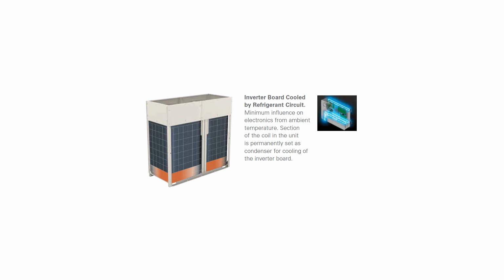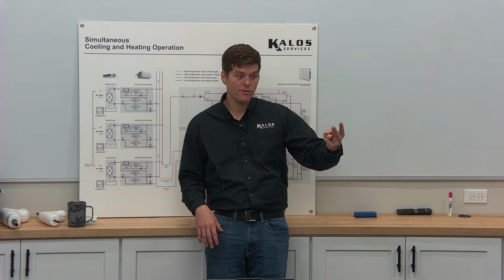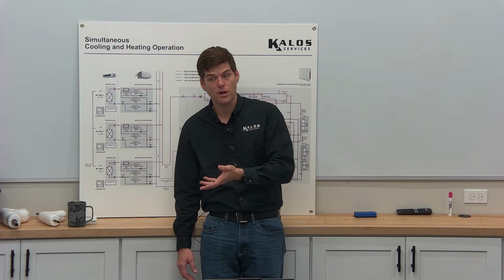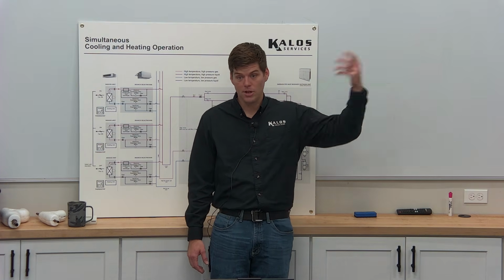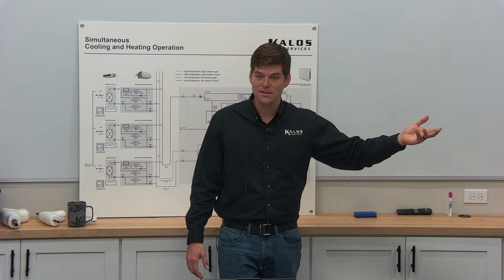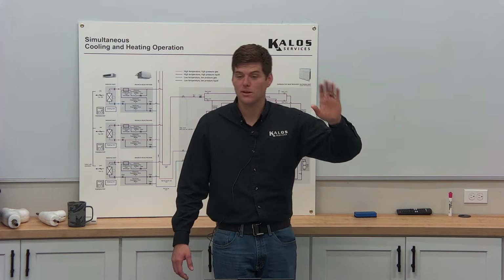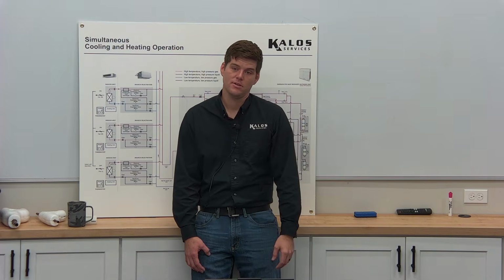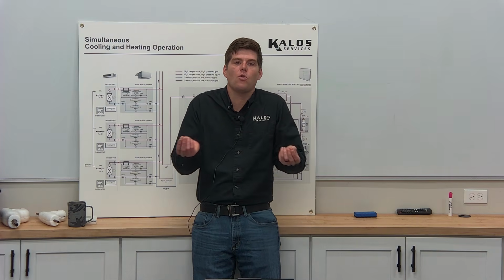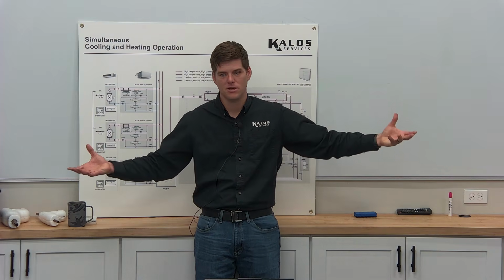You take a 90-degree liquid and you run it across some heat sinks of 2 fan inverter boards and 2 inverter boards for compressors, and you pick up an extra 30, 40 degrees of heat, and then that liquid just gets dumped right back into the liquid line itself. Right? Such a small quantity compared to the entire system itself that it's unnoticeable.